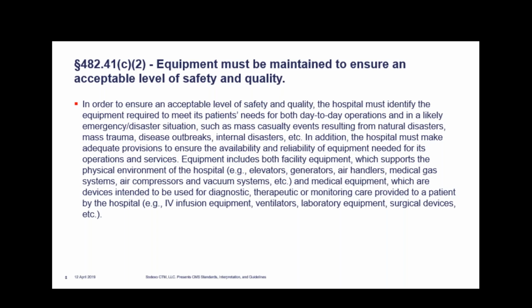Are you seeing the process of any software updates? So they did make us do that, even though the management plan said we did not manage the lab. It doesn't matter. Your management plan can't supersede this location. That's your problem. One of the things you need to remember with DNV is because we require all of our clients to be ISO compliant or certified within 3 years. Even if the equipment doesn't fall under here, if it needs to be calibrated, you guys pay attention to that, because that's a real weakness with a lot of our hospitals: equipment that needs to be calibrated.